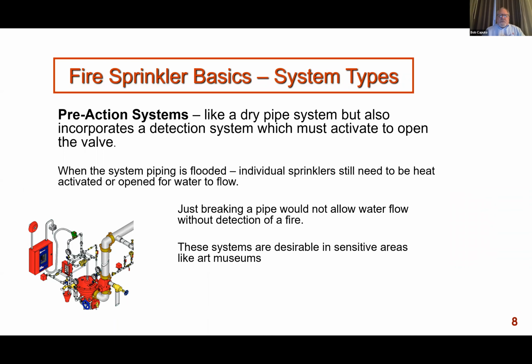Pre-action systems are like a dry pipe system, but they incorporate a detection system, whether heat detectors, smoke detectors, rate of rise detectors, or beam detectors. There's a host of variations of detection systems. But in my pre-action system, I need both the heat to activate the sprinkler and the smoke, or whatever the detector is designed to detect, to also send a signal to a panel, so I have two functions.